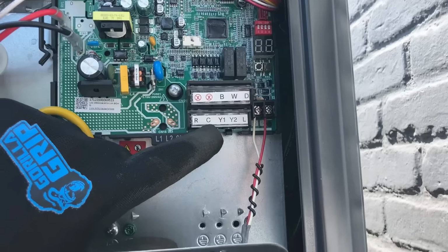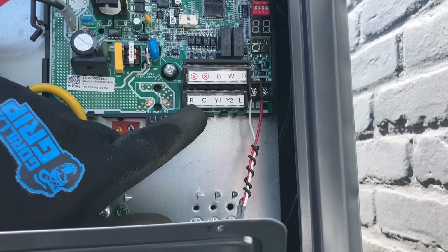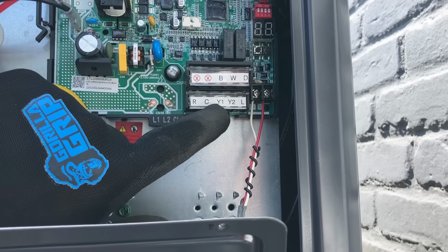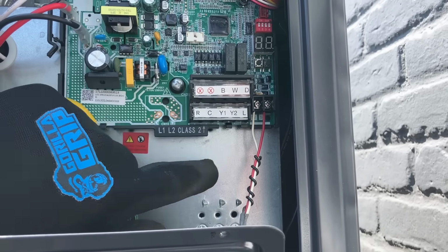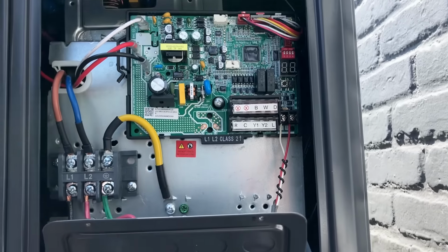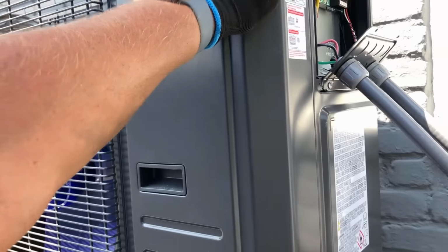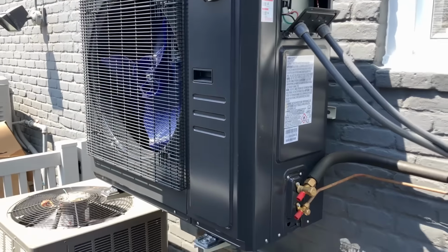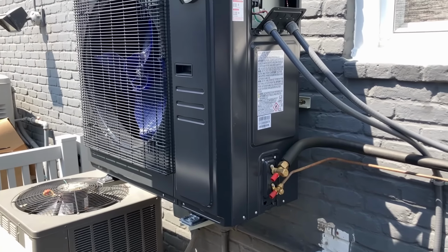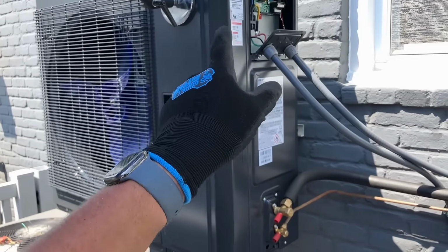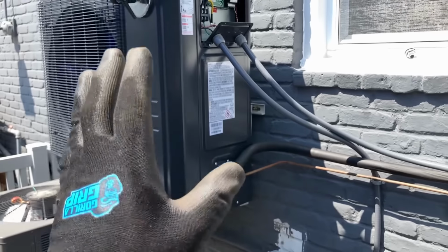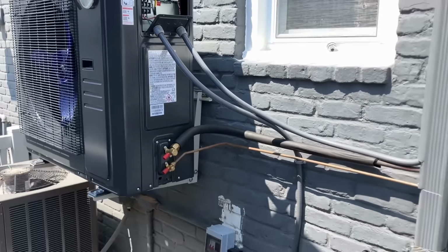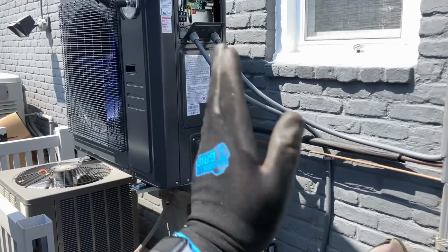But you can also do traditional 24 volts right here. RC, Y1 for first stage cooling, Y2 for 2-stage cooling. This is a side discharge inverter heat pump, so you need that other wire for heat pump, that reversing valve, right? But unless you do S1, S2. This system is perfect when you're doing a straight cool to heat pump replacement.